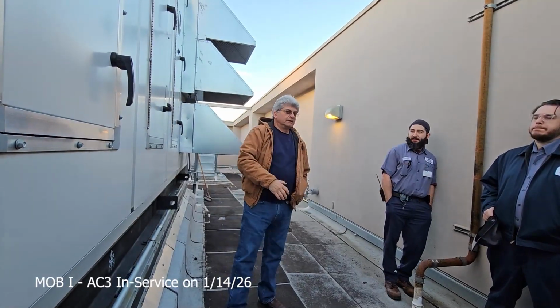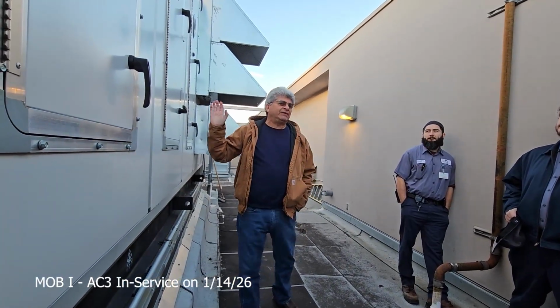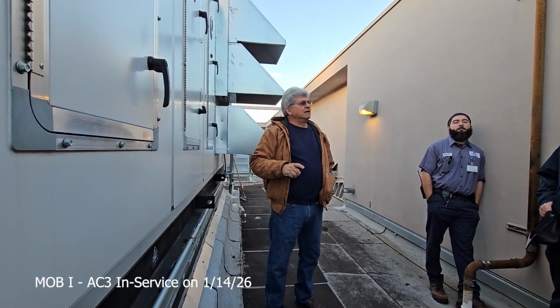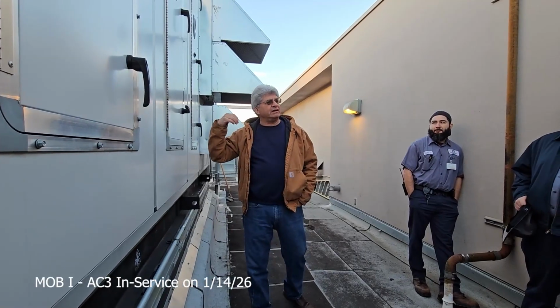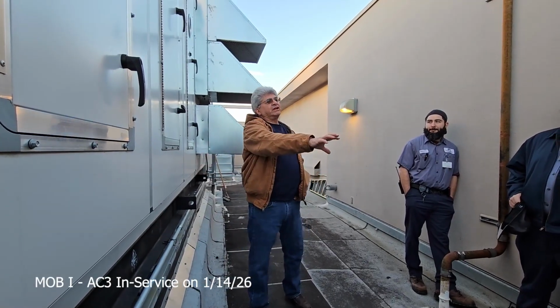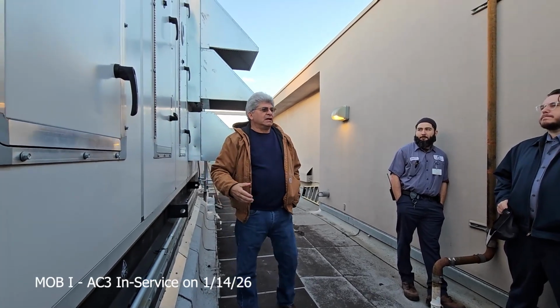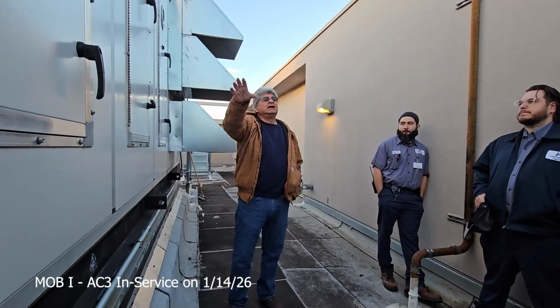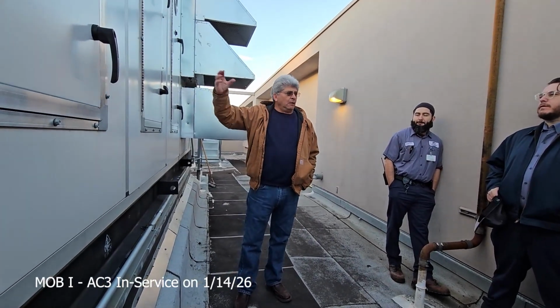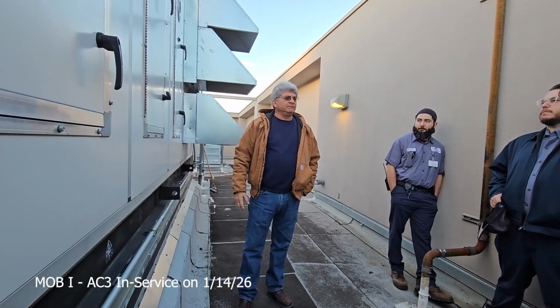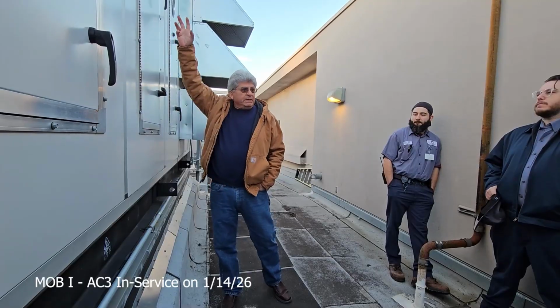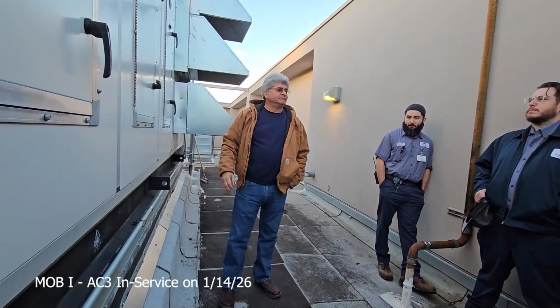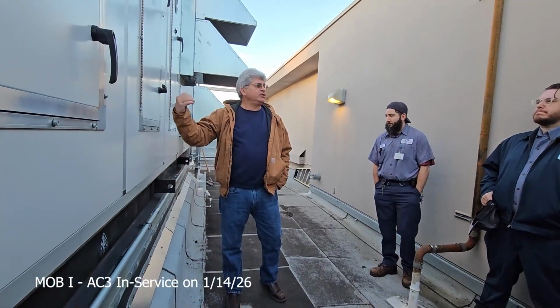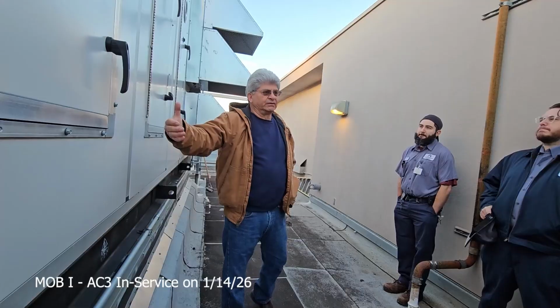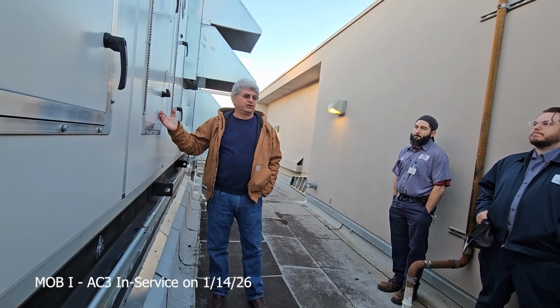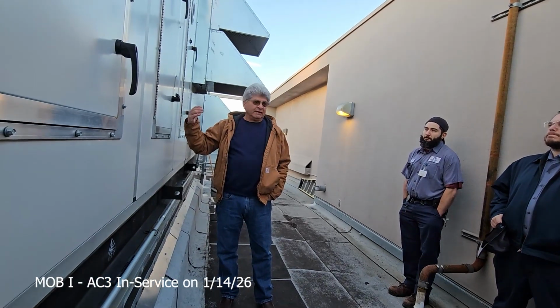Is it a big unit like this? Not quite as big, half the size, but it's 100% outside air, no return air. You guys have return air and outside air. So you're the one that's going to answer that question by looking at them. And I'm sure you guys have a program and you look at your stuff regularly, right? You're going to be looking at this regularly. Your night shift guy is going to look at the filters when the machine's shut down. And he can report back, hey, you got pre-filters, and then you got a set of 4-inch final filters. Your pre-filters are cheap, comparatively speaking. They should be changed regularly.